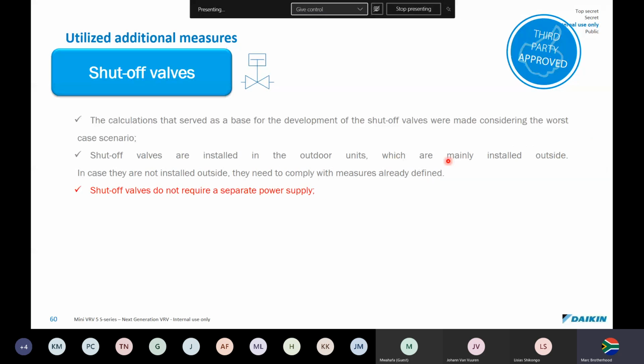If we look at the shutoff valves now, the calculations that served as a base for the development of the shutoff valves were made considering the worst case scenario. Okay, so they considered the worst kind of leaks possible when they made these calculations and incorporated them into the R32 outdoor units. The shut-off valves are installed in the outdoor units, which are generally installed outside. In case they're not installed outside, they need to comply with the measures already defined, which I showed to you earlier on.